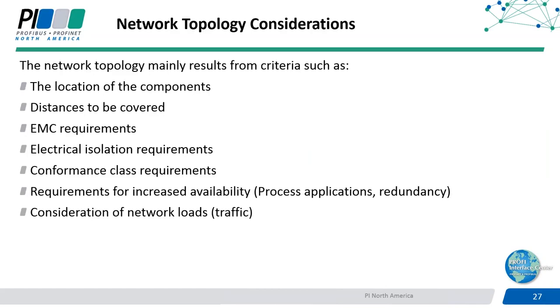The network topology results from criteria such as the location of the components and machinery, as Nelly was showing you on the previous diagram, also the distances between them, EMC and electrical isolation requirements. That's also very important. Conformance class requirements related to PROFINET, for example if you're doing motion control or other special application requirements such as high availability systems for redundant controllers, redundant devices, or redundant networks. And finally, consideration of critical network points where there could be a lot of converging traffic causing high network load.